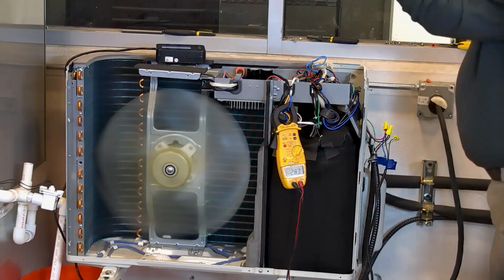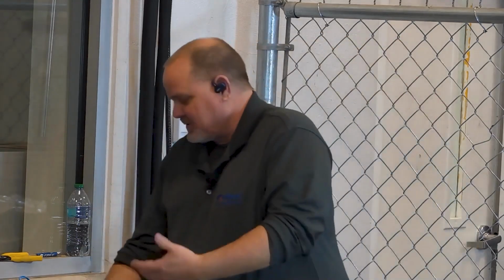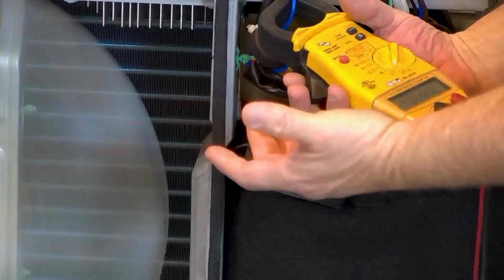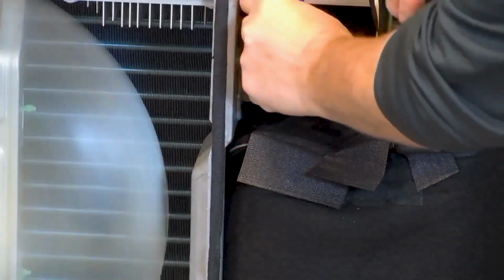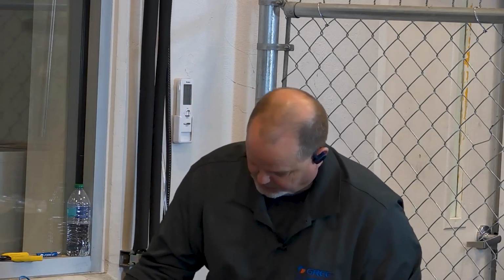So don't be so quick to judge a compressor bad, because you could end up changing that compressor or that outdoor unit, and you could have something stopping up your refrigerant flow. Maybe we didn't open the service valve. Trust me, we've had those phone calls. Haven't we? All the time. When we've got a picture and you're like, the valves ain't open. And they only open one. Yeah. So I guess we could simulate that. Close the valve a little bit, see what it does. They just crack it, and then they don't continue. So I wanted you guys to see, you can absolutely measure the amp draw with an AC amp probe on this compressor. I actually just did all 3 wires.